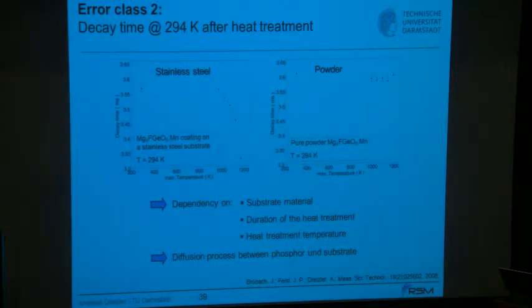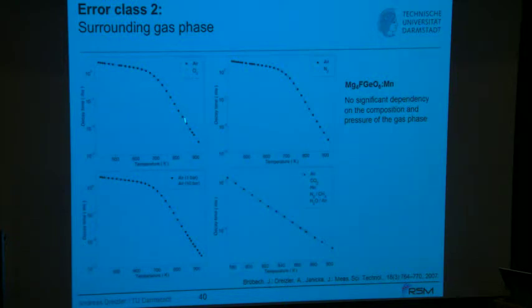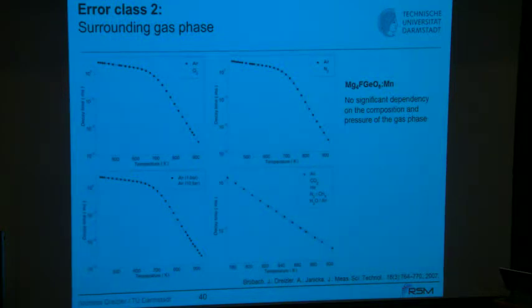The surrounding gas phase can also have an impact. This phosphor was exposed in an oven with a cell that could be flooded with different gases — air, oxygen, nitrogen — and the calibration curves superimposed almost perfectly. Pressure variation and addition of CH4 and water vapor also had no effect. This phosphor is truly insensitive to the surrounding gas phase.